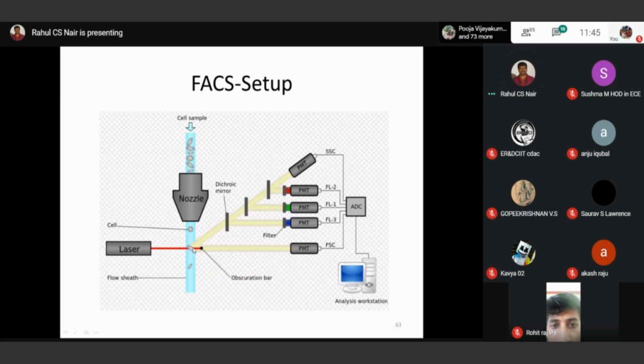There is a laser beam coming from this, and there are several optics. So usually a straight... detectors used are photomultiplier tubes because of the very feeble light from these cells. So they are finally collected to the ADC and processed. So this is the basic thing. The core portion is this nozzle, that is the hydrodynamic focusing.